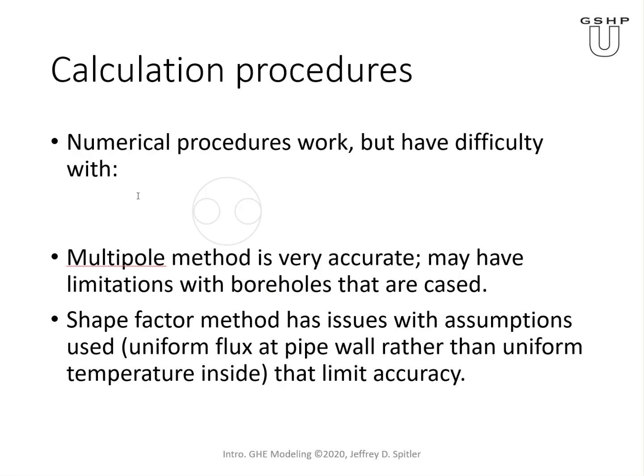Going back to the different methods: numerical procedures can work, but they generally have difficulty. For example, a borehole with a U-tube where the tube has been pushed up against the wall is very difficult to fit with any kind of gridding approach. It eventually becomes tangent and forms a wedge-shaped curving gap, which can be hard to represent accurately on a grid, making the procedure difficult to use.